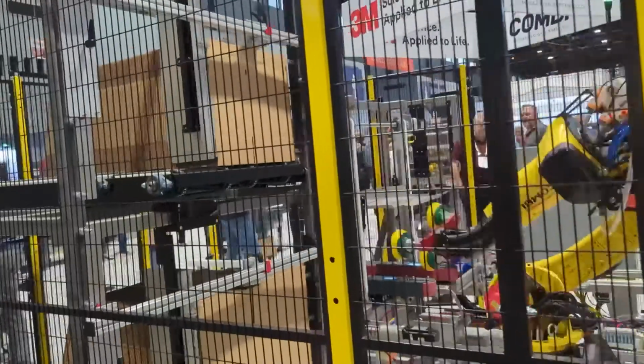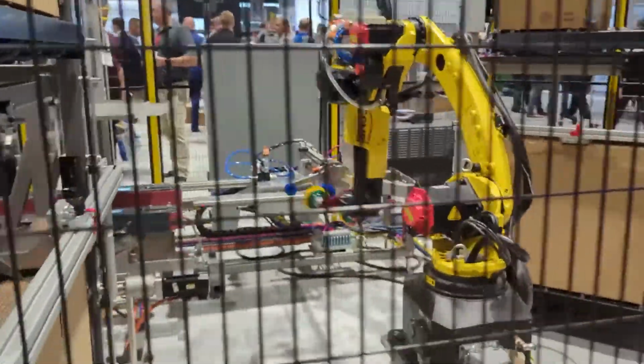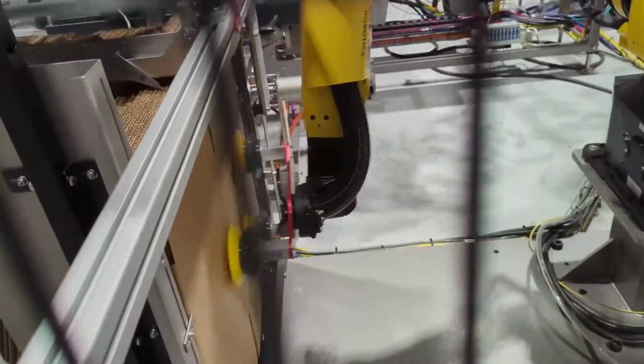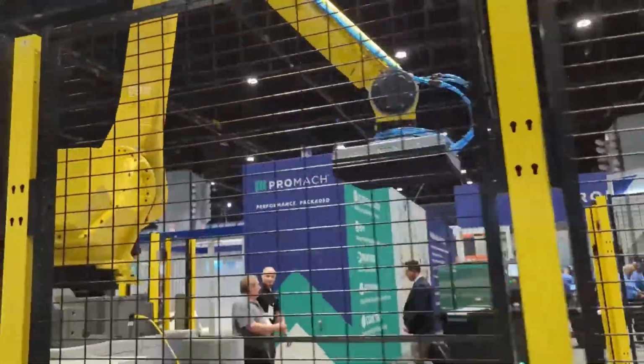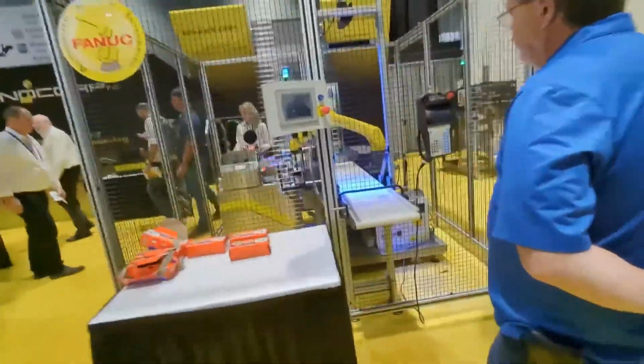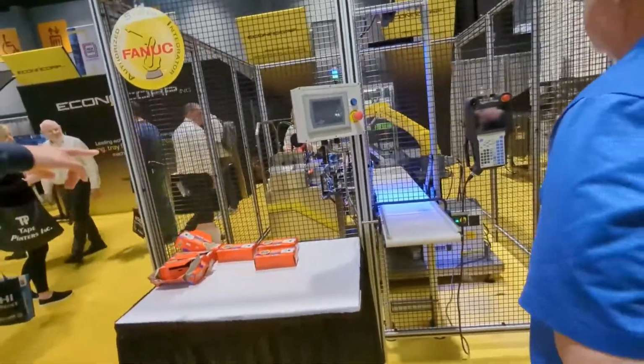And like I said, there's a lot of applications that are going out with robots with big chunks of metal on it, sharp metal, pinch points in the application from where it's doing its pick and place. And you have to be more cognizant of that because before, your robot was generally inside of a cage. And with the way we engineer our systems, you had to hit a safety interlock button. The system itself had to give a signal back from the PLC, the robot, all the pieces of equipment in there saying, hey, I'm safe, it's okay to enter. Then once you open the gate, it safely, safety rated, shuts down all the pieces of equipment.